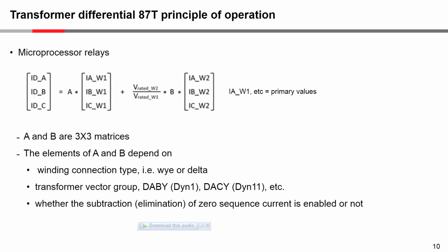Just a point to note now is when we look at these matrix equations, all quantities that I will show here are primary values, okay? So IA winding 1, IB winding 1, IC winding 1, for instance, are the actual primary currents flowing A, B, and C on the winding 1 side. And then you can see in the equation there, V rated winding 2 to V rated winding 1. That will be the rated winding 2 primary voltage and the rated winding 1 primary voltage. And that ratio is what converts the current magnitude on the winding 2 side, the magnitude compensation or conversion, to convert those currents to winding 1 side current values.